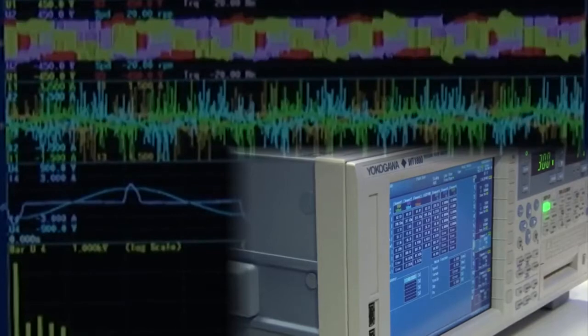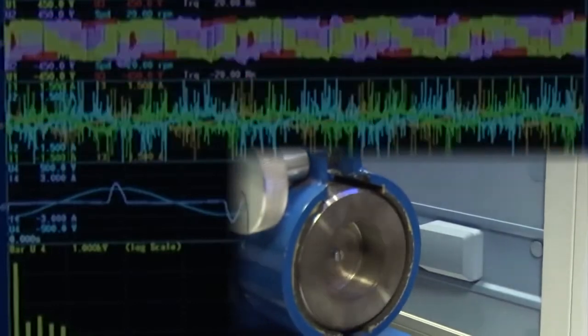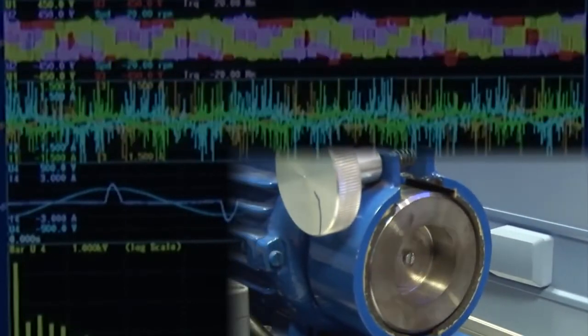A single WT1800 enables users to measure power, frequency and motor output in order to measure the inverter, motor and total efficiencies. The motor version of WT1800 makes it possible to simultaneously monitor changes not only with voltage, current and power but also with rotation speed and torque caused by the dynamic load.